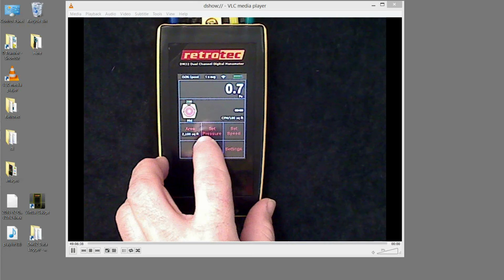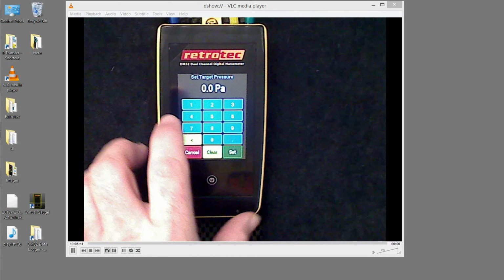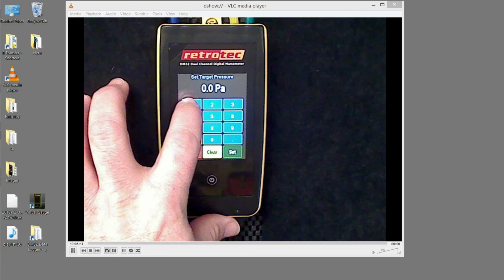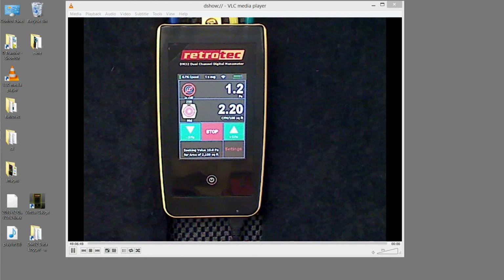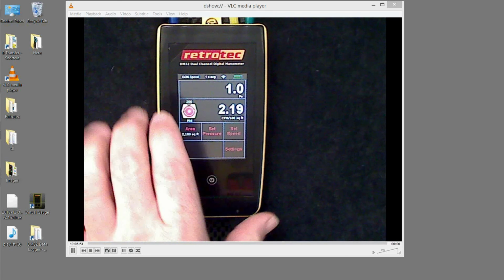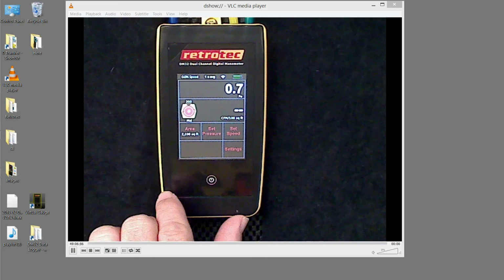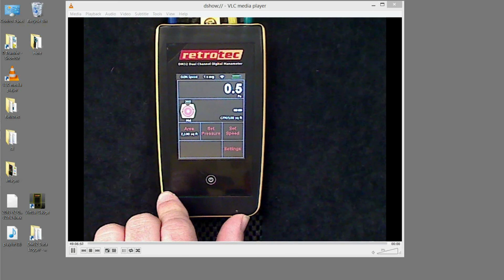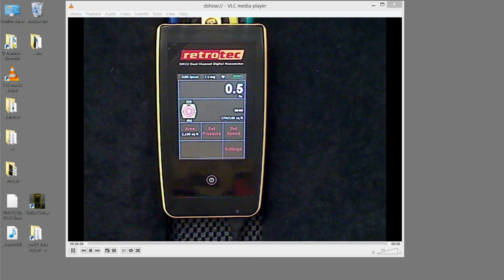And I can set it also, when I train a lot, I also just set it to 10 pascals so I can get results and still talk over the fan. But I do not need a tablet or a smartphone or anything else to actually use all the features that the gauge does. It will create its own Wi-Fi signal if I needed to.